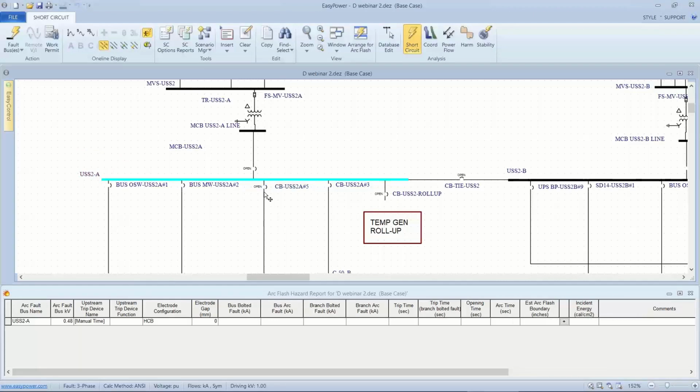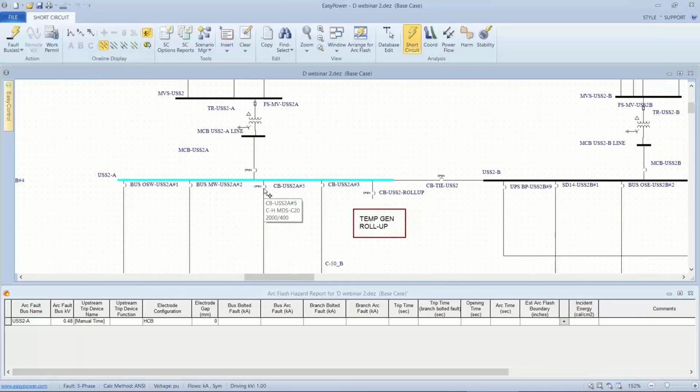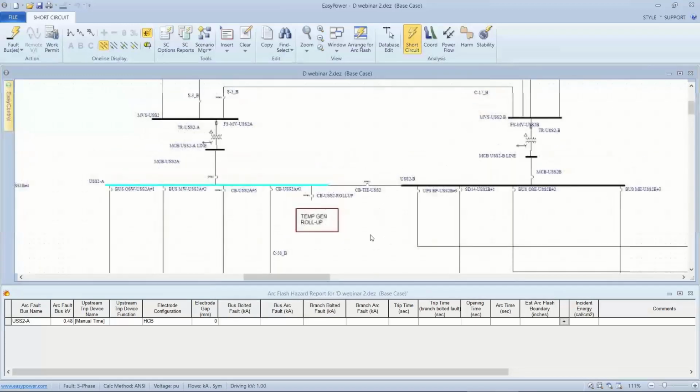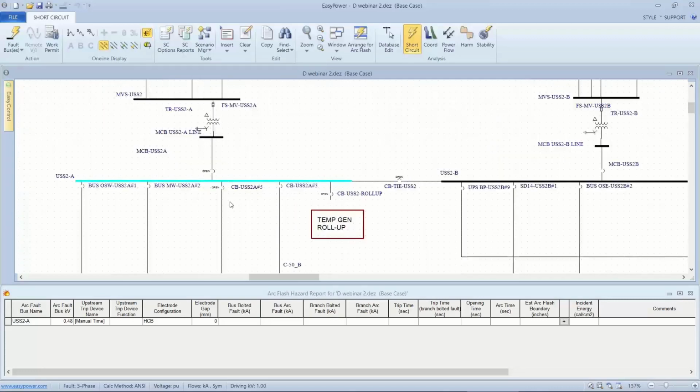And it's a result of that one load. So this goes back to my discussion about, well, maybe we need to have an understanding of where this current is coming from and does it really make sense. And it turns out in this particular case, it's from a bypass around a UPS. And so it may not be something that's realistic as far as normal operations.